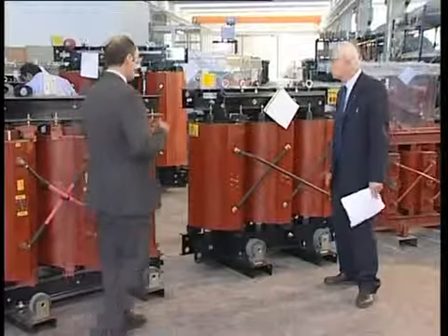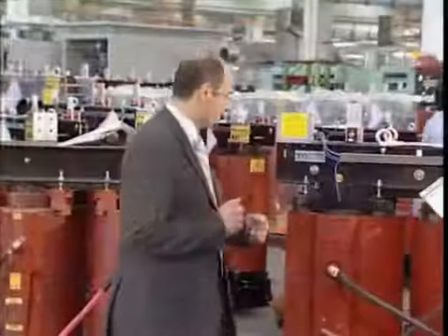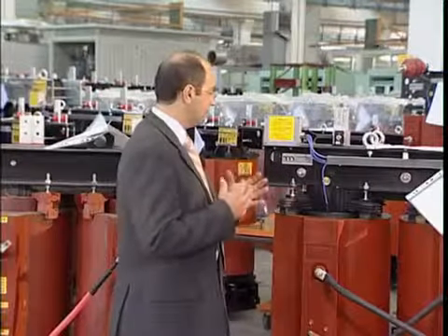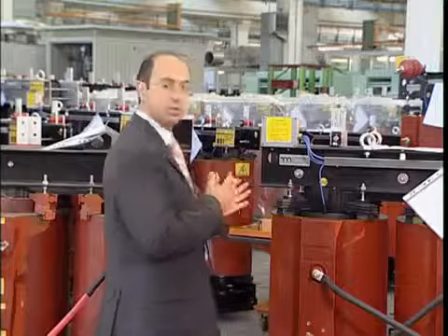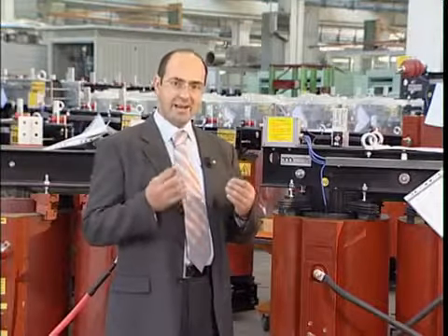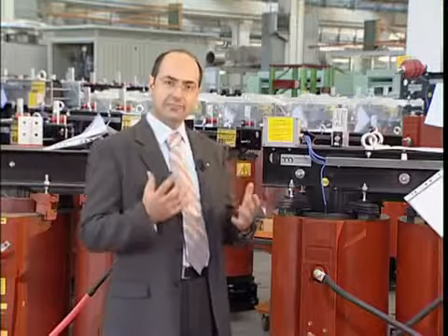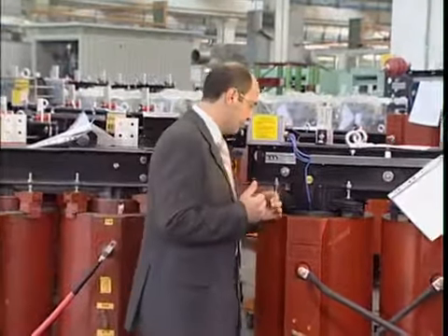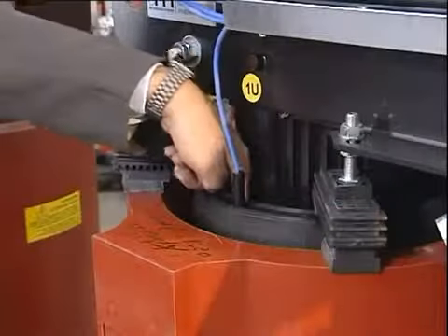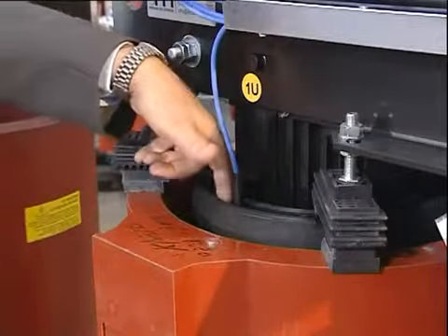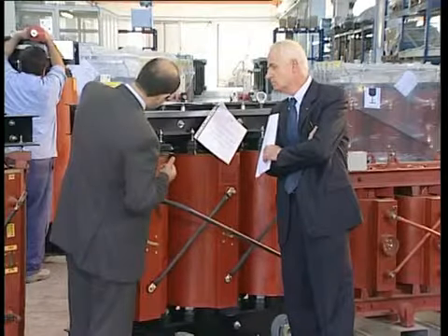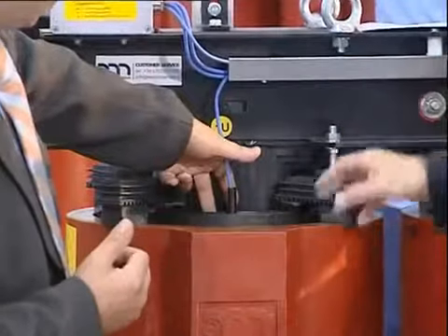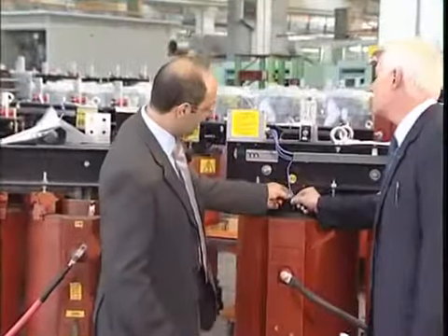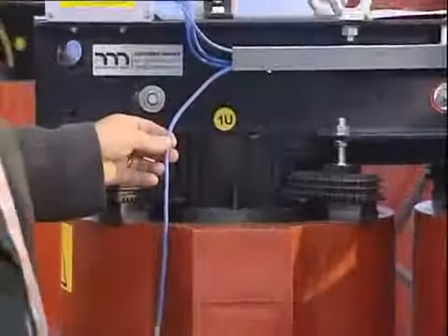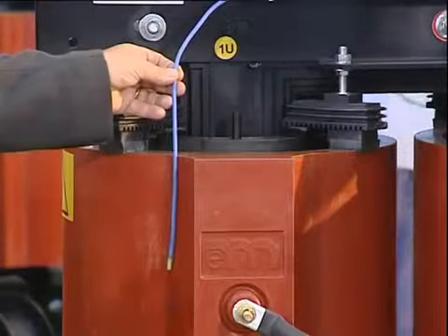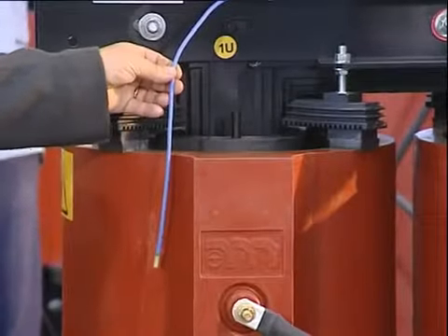What else? Then let's analyze these transformers in detail. Let us observe, for example, the natural cooling system of both transformers, which, as we said, is one of the crucial parameters determining a transformer's reliability. Here we can immediately see the low voltage winding with a large central ventilation duct, where I can insert my finger, and a duct between the core and the low voltage winding, where also a finger can go through. Is the probe extractable again? The probe is again extractable, located in the upper part of the winding. In a critical area? Exactly, in the hottest part of the product.